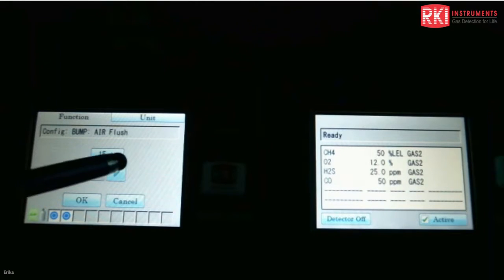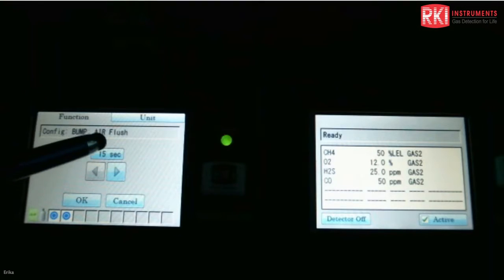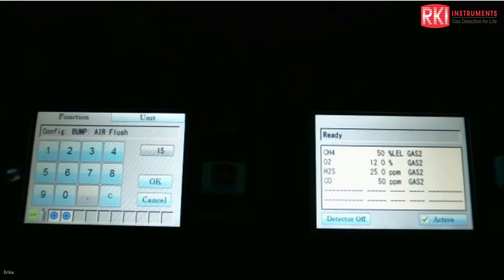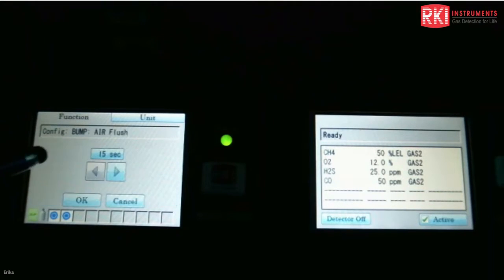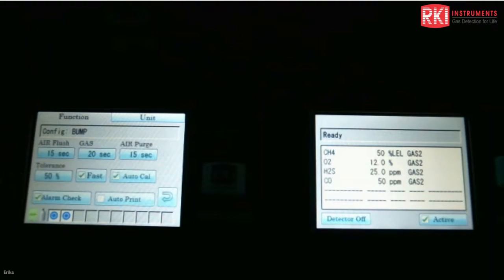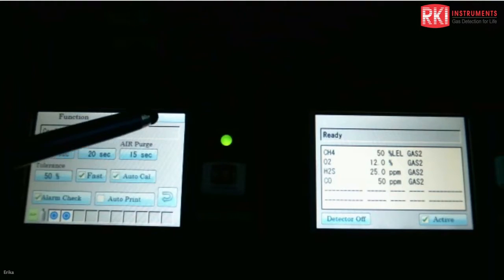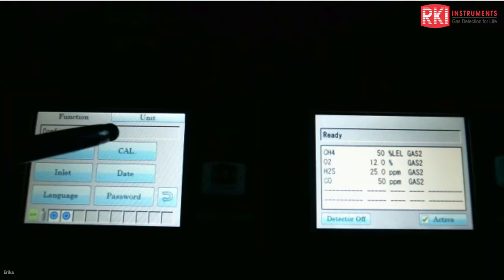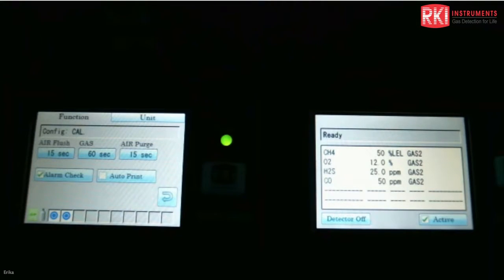You can change the air flush and get the number up. 15 seconds is the lowest. You can also click it and put whatever number you need. So I'll just put 15 on there. Okay, 15 seconds on there, and okay. And go back. And then let's go through the cal, which is similar to the bump. It just gives you the air flush time, gas time, and air purge time. Also the alarm check you can also do on there, and auto print as well.